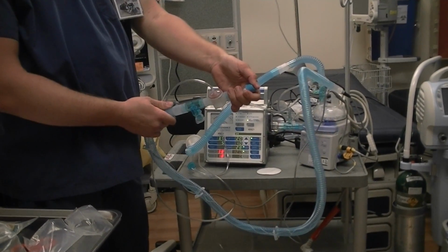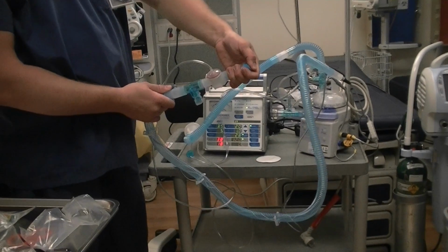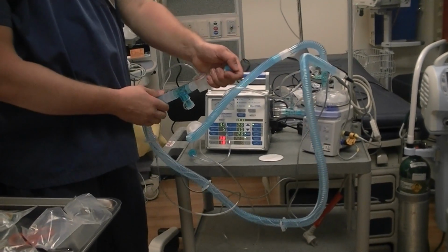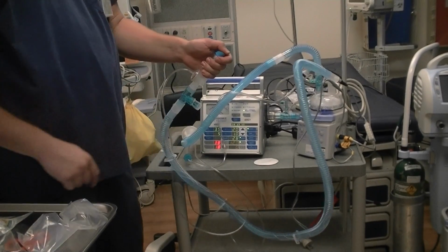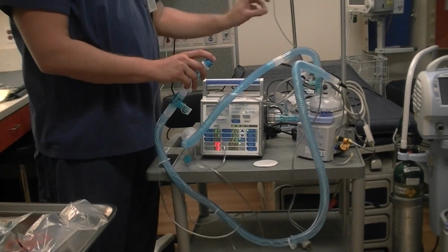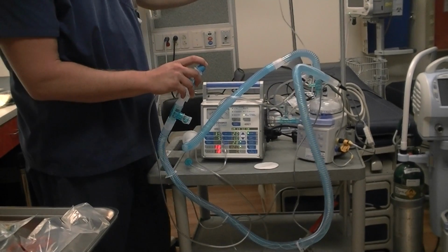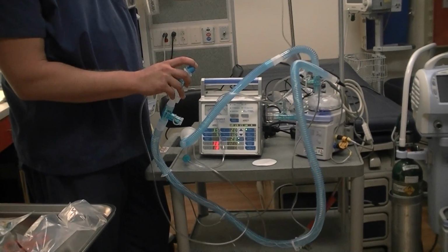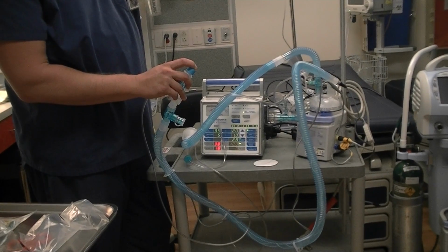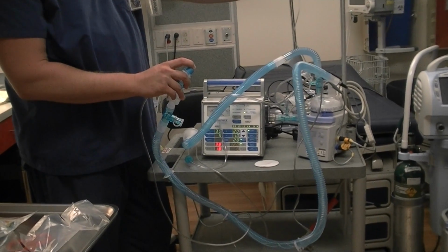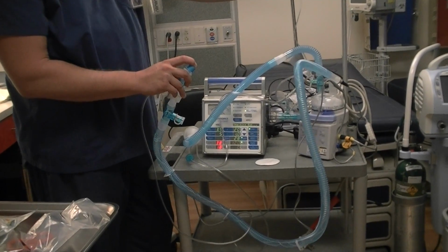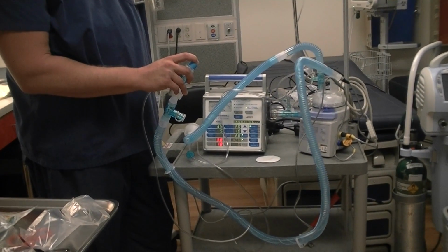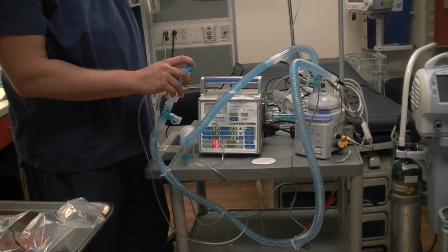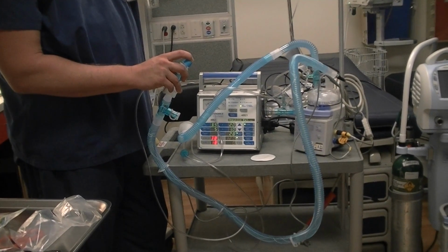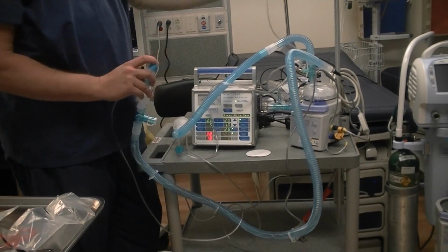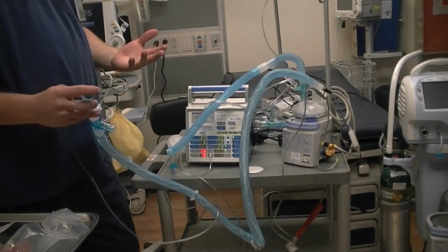I would hold on to the tubing here, or I should say the cap, just so it doesn't blow off because it is putting pressure through the circuit. Like I said, you could pinch off your line to your water. Okay, so it says press on to vent. That means that we passed our cal.